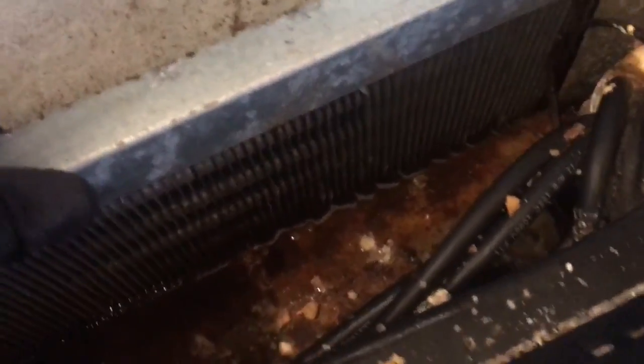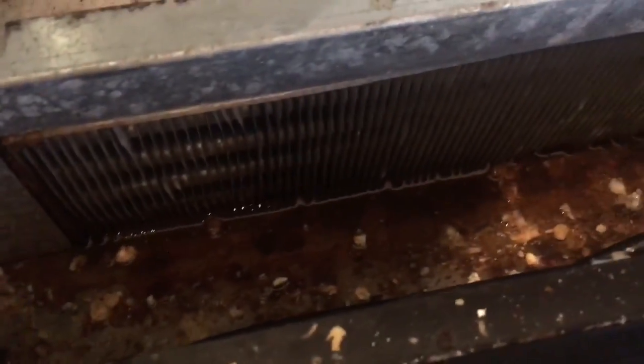There's a big old drain right there. I'm going to get my shop vac and do a bunch of cleanup. We'll get her good and cleaned up so that coil can drain. It's not draining — the water's kind of standing.